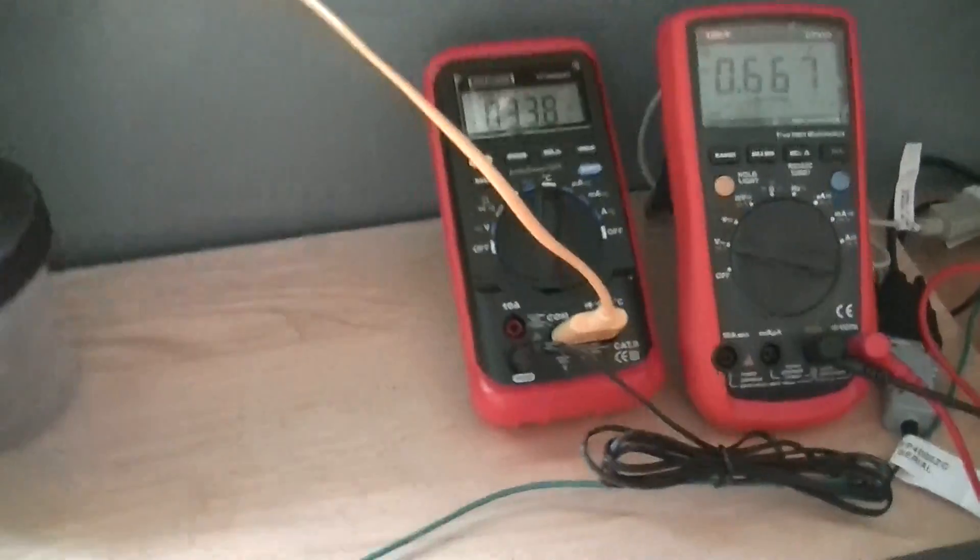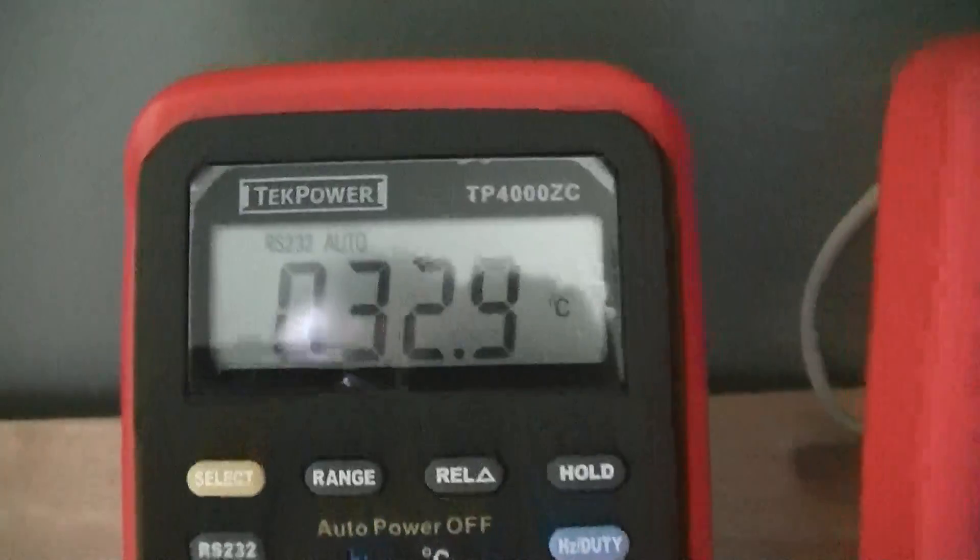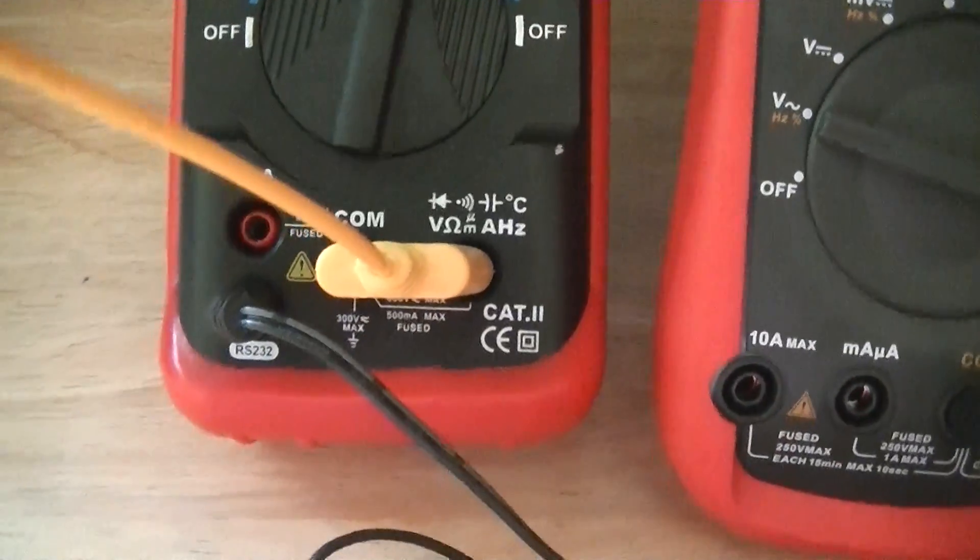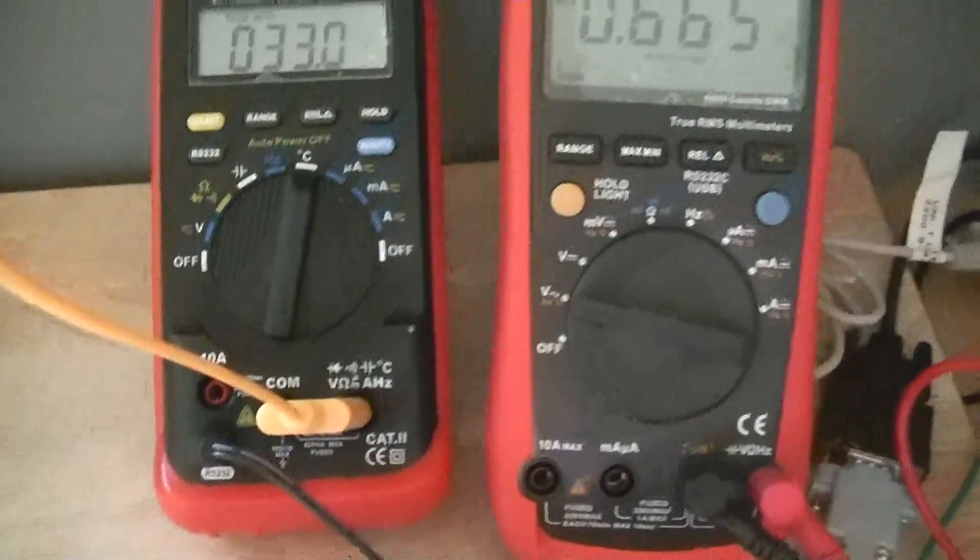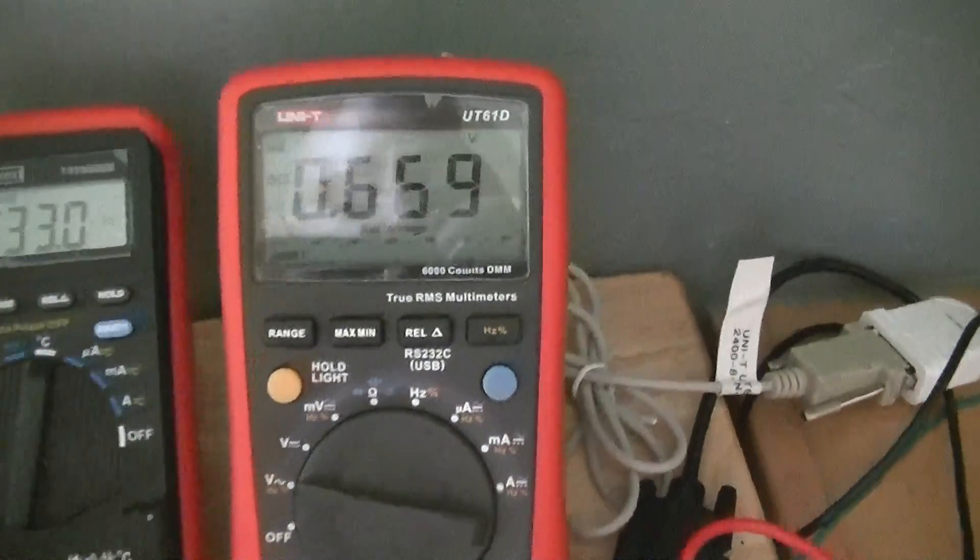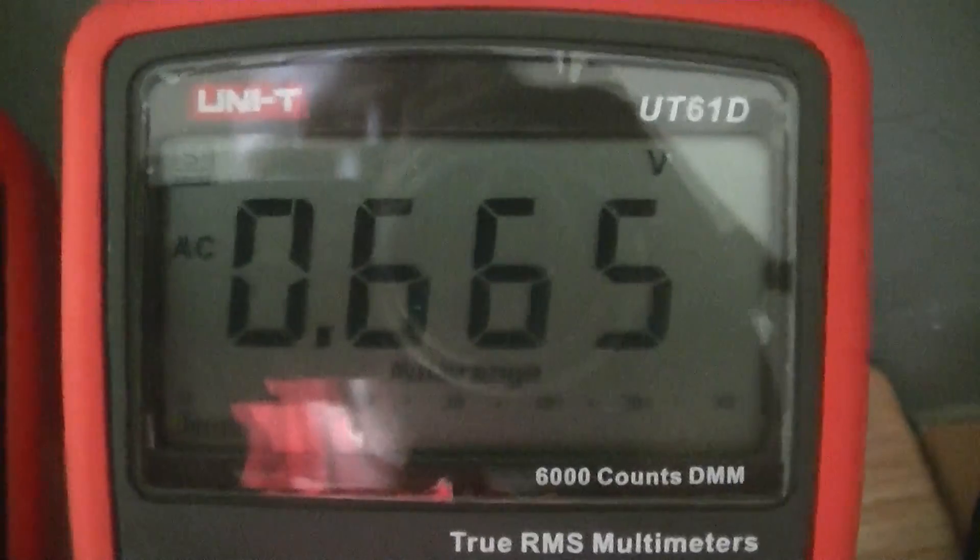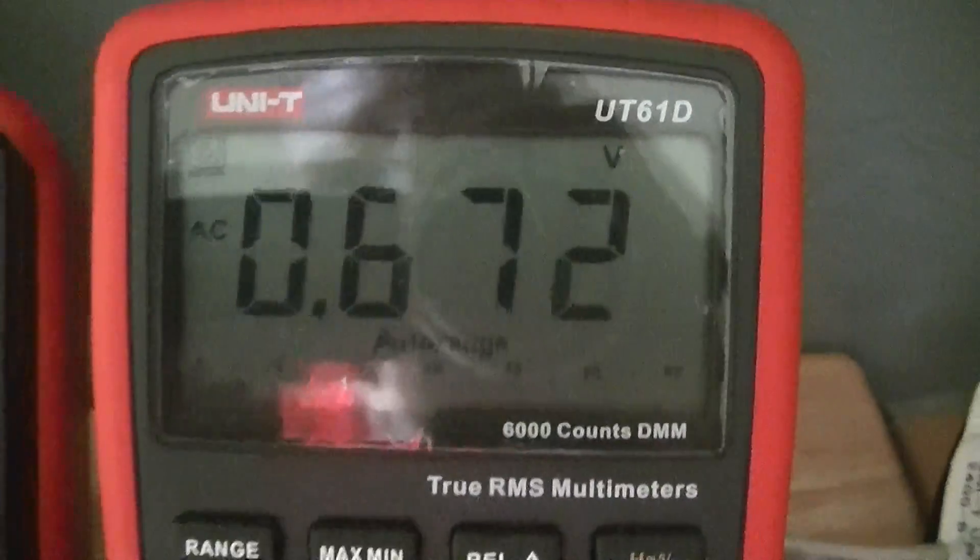This one is actually measuring air temperature. The reason why we have the TekPower TP4000ZC measuring temperature is because in my area, in Tucson, Arizona, the stray voltage follows temperature in air conditioning season.